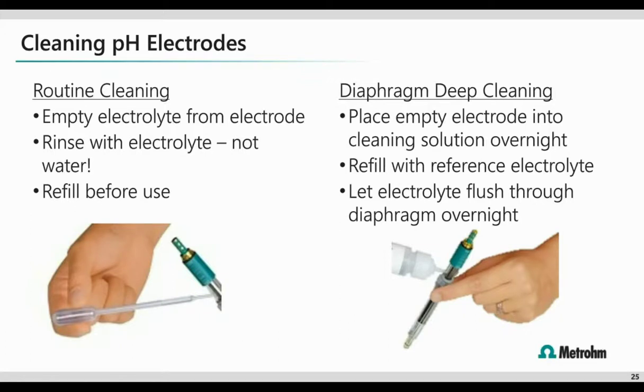When it comes to selecting a cleaning solution, that will really depend on what your contaminant is, what you're working with. For example, if you have silver precipitates, those typically respond really well to a 7% thiourea and 0.1 molar HCl cleaning solution. If you're dealing with some really stubborn protein deposits, we can remove those with a 1% pepsin in 0.1 molar HCl. For fats and oils, simply use a suitable solvent. So try something like IPA. If that doesn't work, you may have to go with toluene or xylene or something.